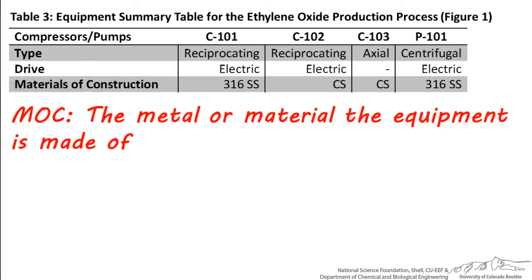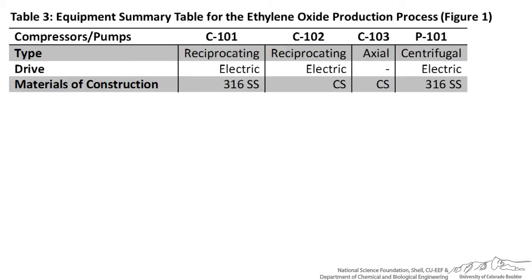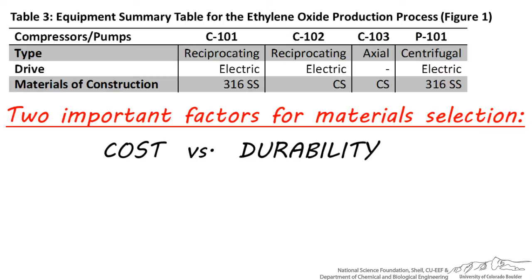Materials of construction is often abbreviated MOC, and is the specific metal or material which the piece of equipment is made of. Selecting the right MOC is important because the process fluid will be in contact with this surface, so it must be able to withstand the temperatures and chemical exposure to the stream. ChemCAD or Aspen will not select the appropriate material for you — you must select this by weighing two important factors: the cost of the material versus the durability required to withstand the temperatures and chemical components.